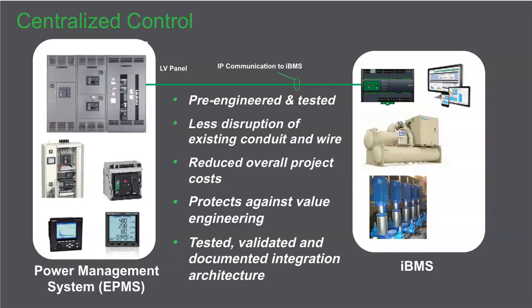When you look at the expertise on a power meter, building management systems aren't the expertise unless an electrician's installing it. I've walked buildings where sub-meters weren't set up correctly, because they probably didn't know the max power, min power, or parameters from the electrical side. If it's already installed by electrical at the beginning of the job, a lot of that's set up correctly, because that's their specialty. So you make sure it's working, with less disruptive conduit and wire when adding external meters. That doesn't eliminate all of them, but the more you can eliminate duplication between specification sides, the better.